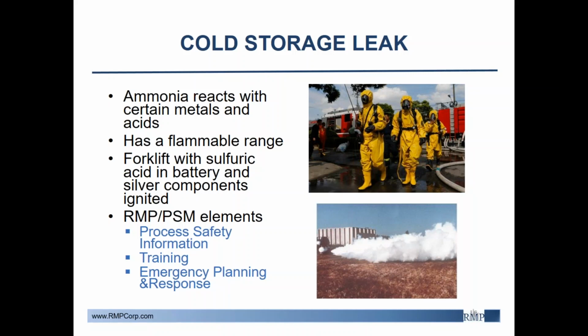An ammonia explosion occurred at a cold storage facility in Shreveport, Louisiana that claimed the life of one responder and significantly injured another. There was a leak in one of the small freezers, so responders used information available in the National Institute for Occupational Safety and Health manual to determine the proper PPE, including self-contained breathing apparatuses and suits. The goal was to get close enough to work on the leak. Unfortunately, what was not known is that ammonia can ignite at certain concentrations and reacts with certain metals and acids. However, it was classified as a non-flammable gas.